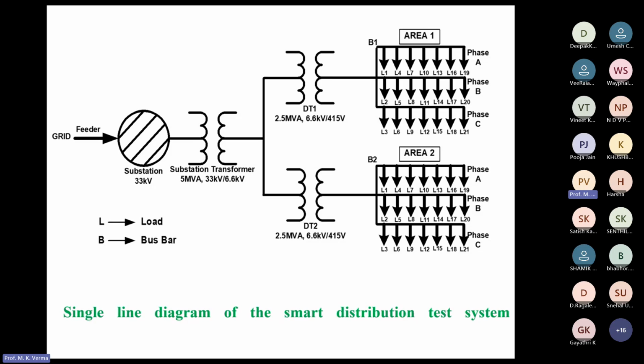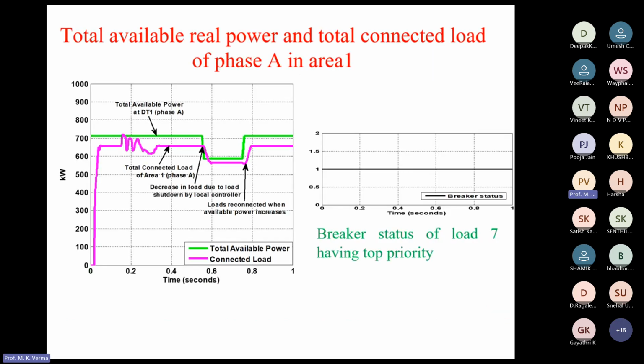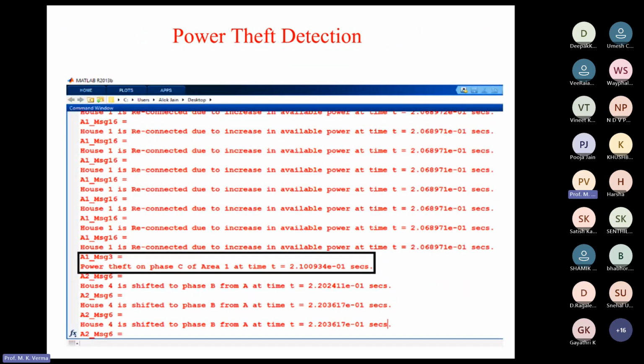It has a 33 kV substation, and there was a master substation transformer, 5 MVA, 33 kV/6.6 kV. He considered two distribution transformers where local controllers were put, and a master controller was put at the substation. He considered two areas, each area consisting of 21 loads, and then case studies were performed. These are different results. You see, for theft detection, somewhere an alarm is generated in MATLAB. This alarm was generated in the program. It is shown here.